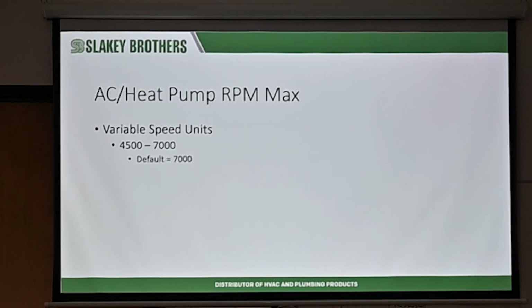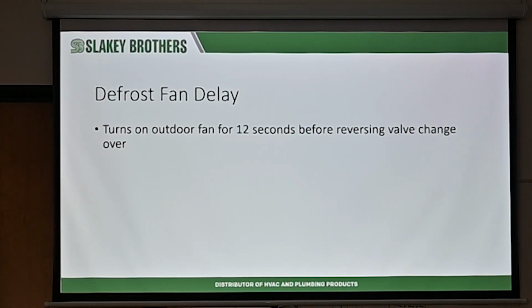Don't mess with this one. Again, an example is if you're doing an addition on the variable speed system and you want to make sure it doesn't go way too high because it's too big of a unit right now. You can adjust it, but again, usually you don't have to do anything with the variable speed stuff. Same thing, defrost delay, that helps out for that quiet mode.